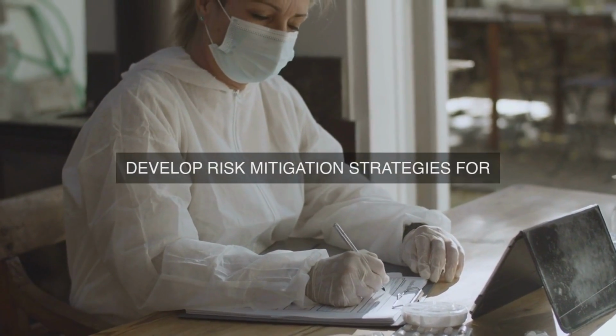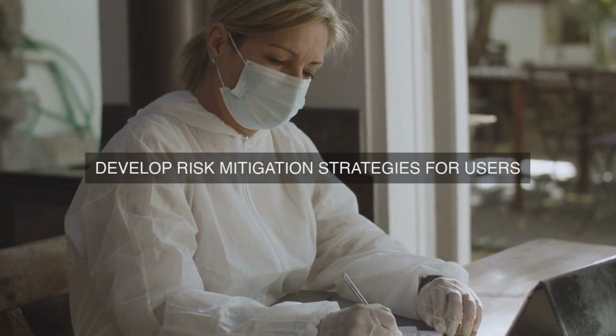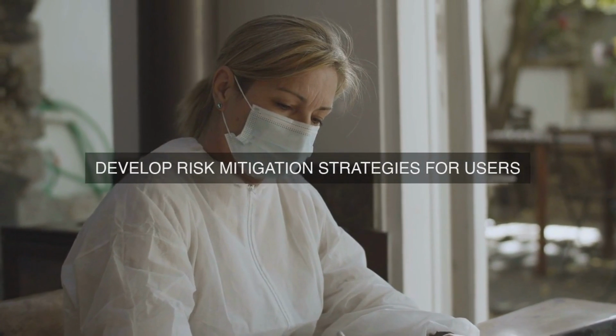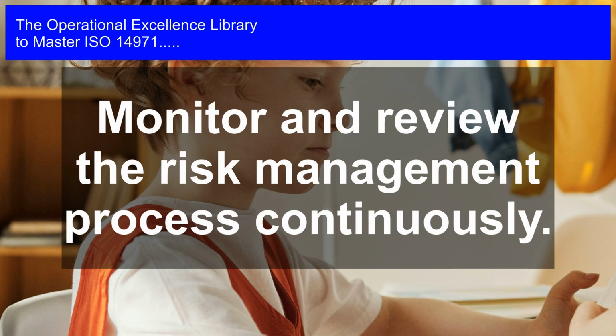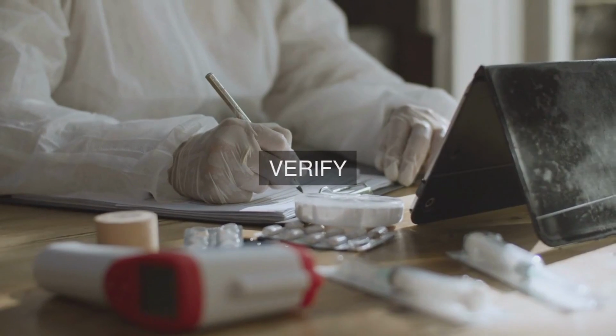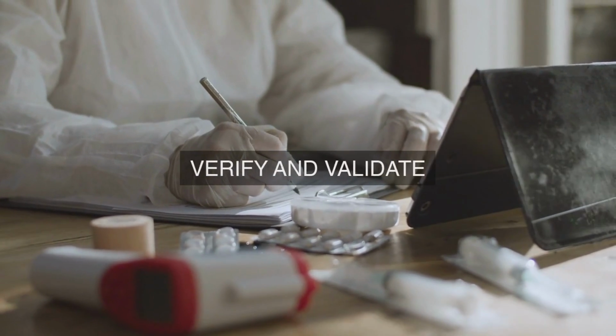The risk management file should be updated regularly to reflect changes to the device, new data, or emerging concerns. In addition, ISO 14971 emphasizes the importance of post-market surveillance, which involves monitoring the device's performance in real-world settings to identify potential hazards or risks that may not have been anticipated during the design and development stage.